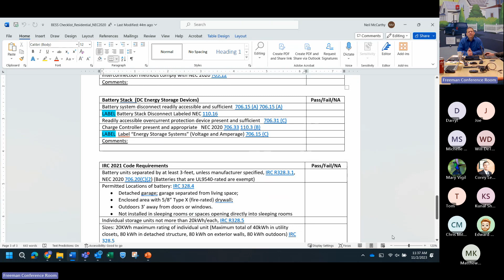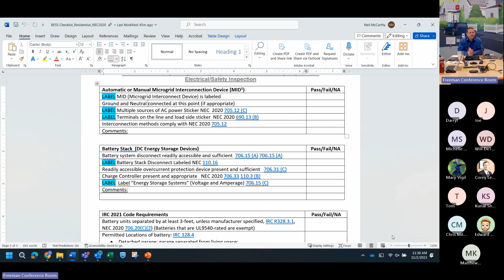For the battery stack, I really recommend using UL 1740 and UL 9540 rated boxes. If this were my house, I don't think I would do anything else, honestly. You want to be able to say you've done everything you can to mitigate that risk. And like I said before, even if you've done everything right, followed all the manufacturer specs and made sure there's no damage, you could still have a fire. That's a scary thing from a solar installer's standpoint, because installers don't like roof leaks and they definitely do not like fires.